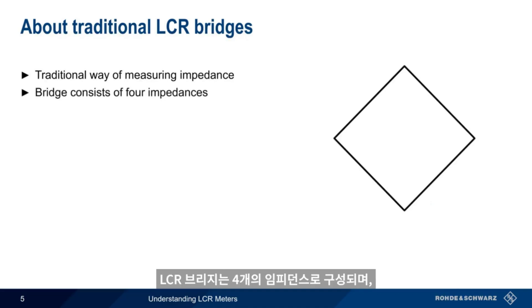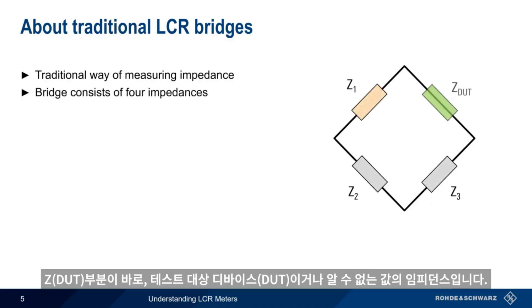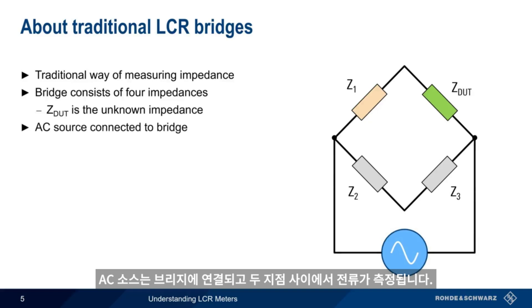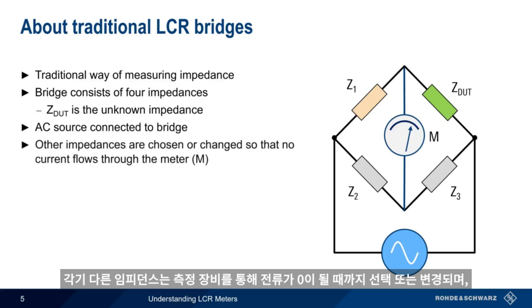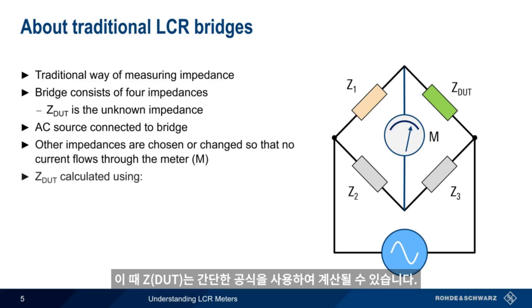The traditional method for measuring a complex impedance is using a so-called LCR bridge. An LCR bridge consists of four impedances, with Z being the device under test or unknown impedance. An AC source is connected to the bridge, and the current is measured between two points. The other impedances are chosen and/or changed until the current flowing through the meter is zero, at which point Z can be calculated using another simple formula.